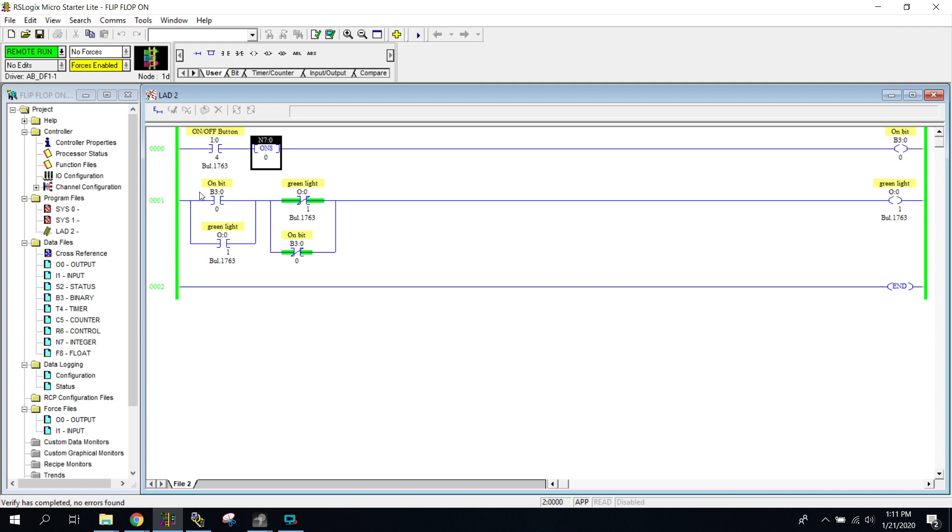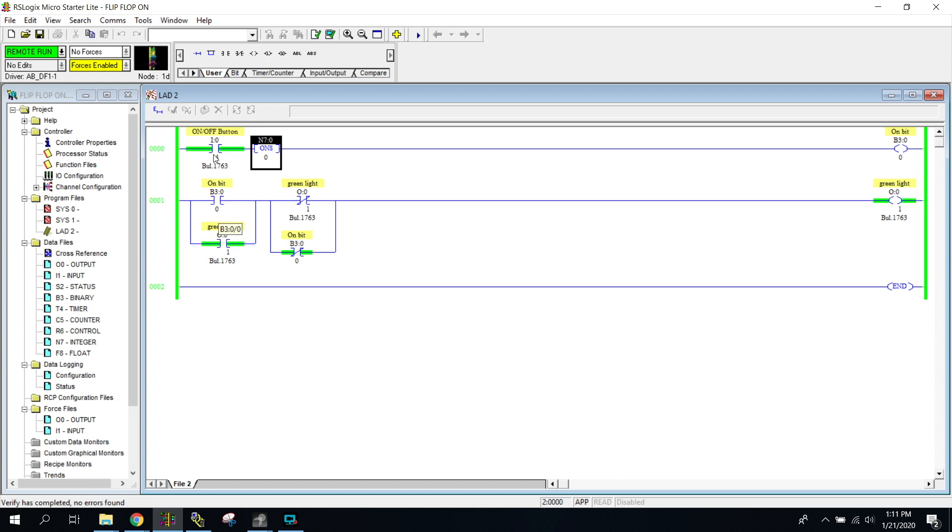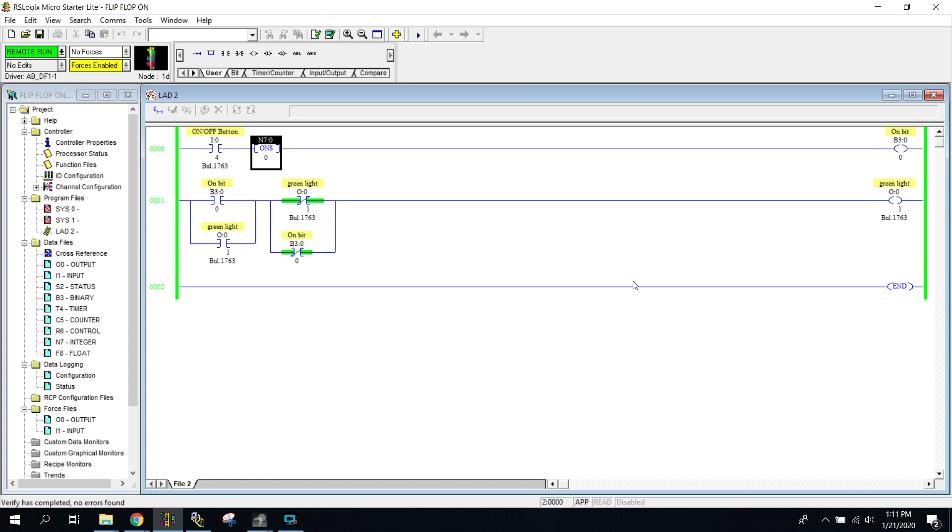Here's our program. You can see up here in the top left corner we have our on-off button. We press our on-off button and you can see that it becomes energized while I'm holding that button in. What it's doing is it's a one shot, so that one scan of the program is coming here and it's turning on our B3.